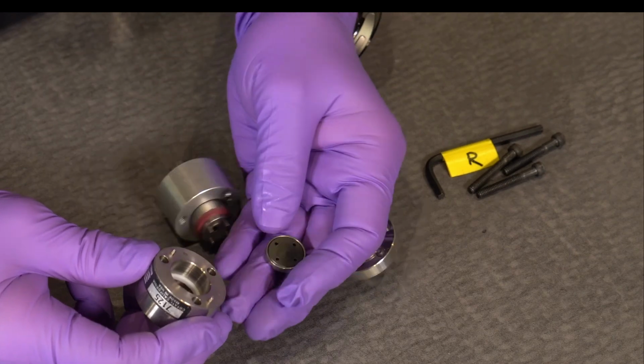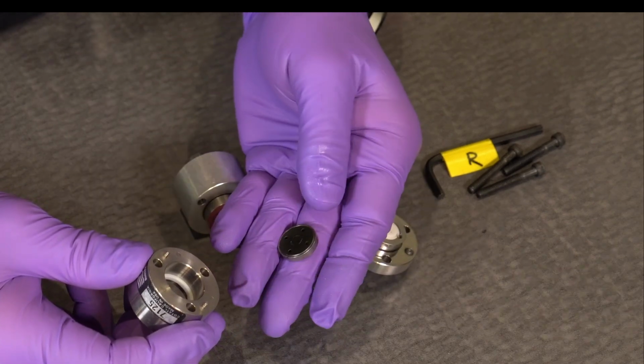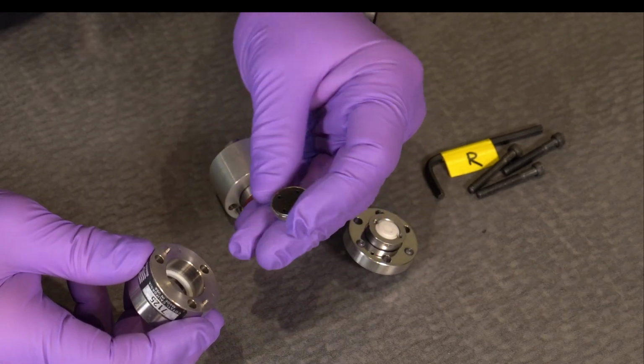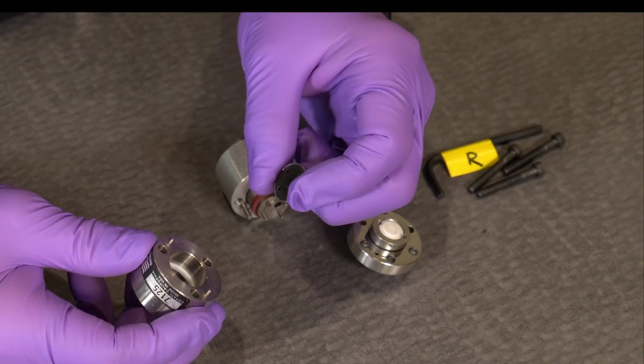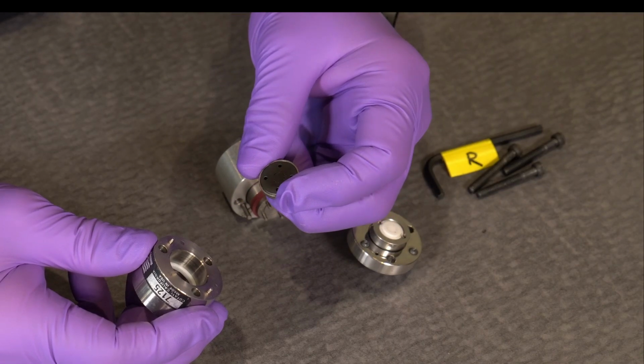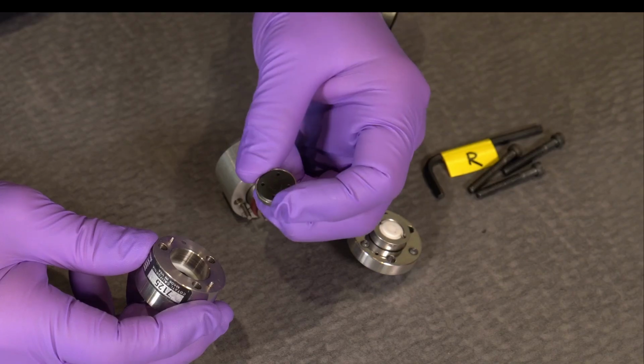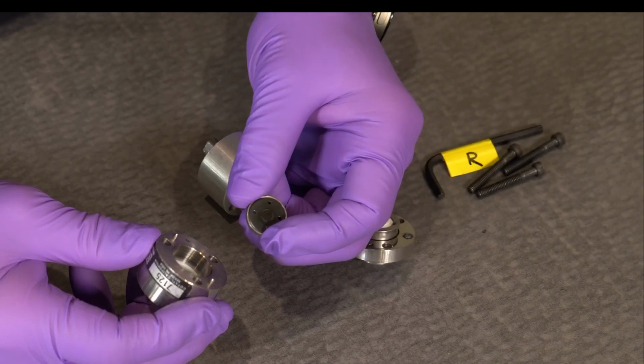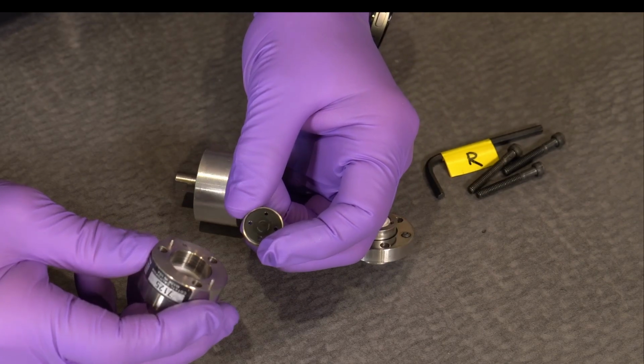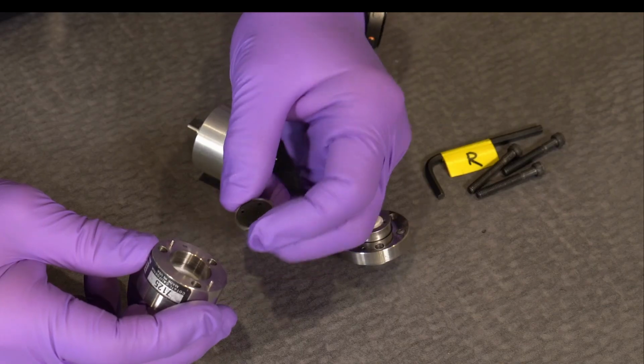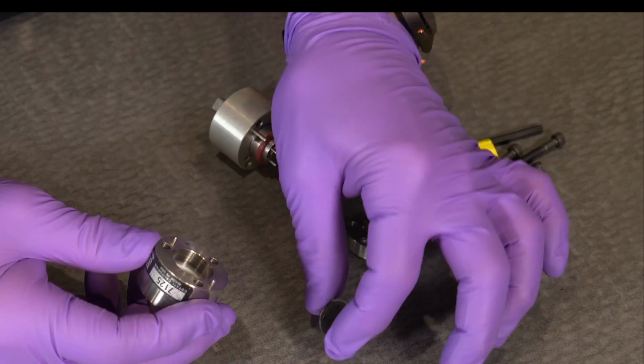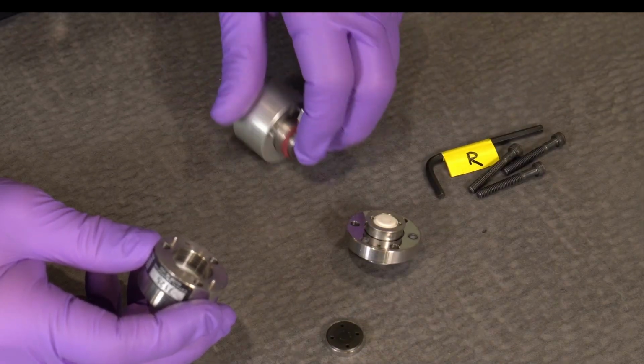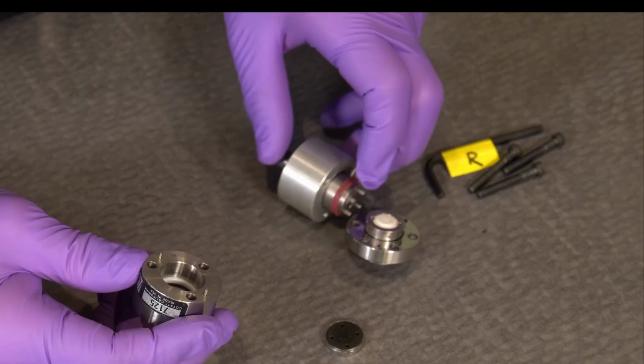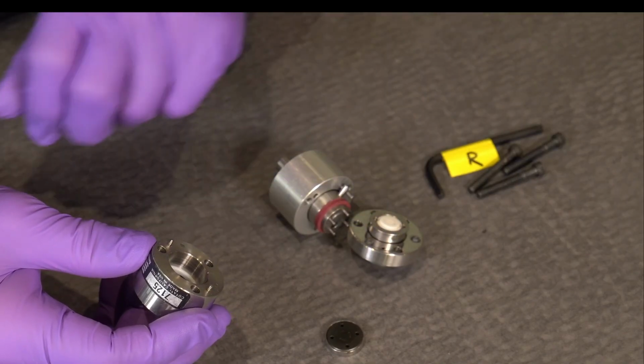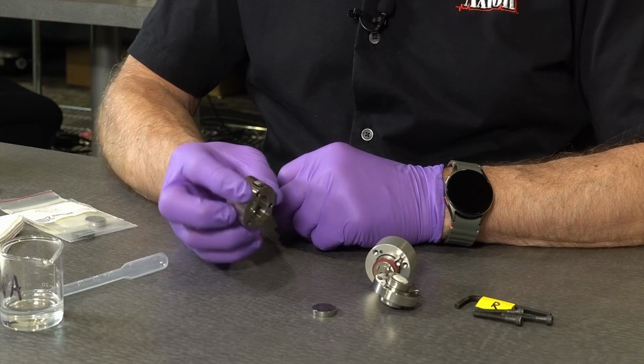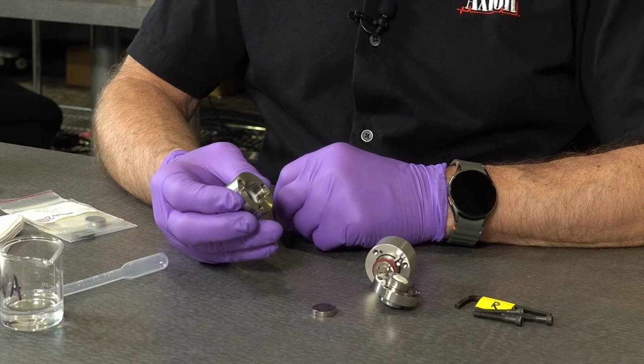And this is the rotor seal. This is the part that gets damaged. Over time it wears out, and when it does, it hurts area and height reproducibility, so you're injecting the wrong amounts of material. When we replace the rotor seal, there's another little secret piece that we replace, called the isolation seal. The best way I can describe it is to stick your finger in there and see what happens.